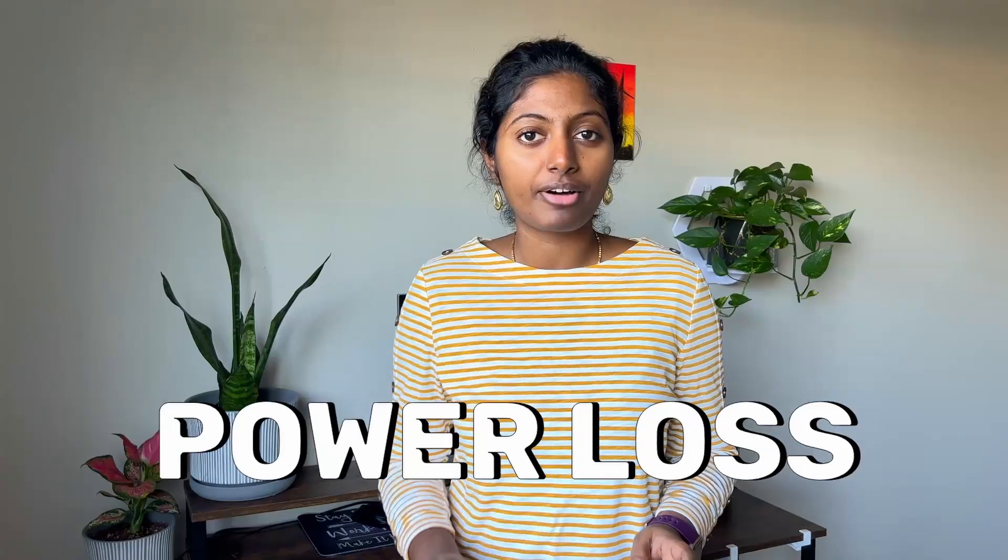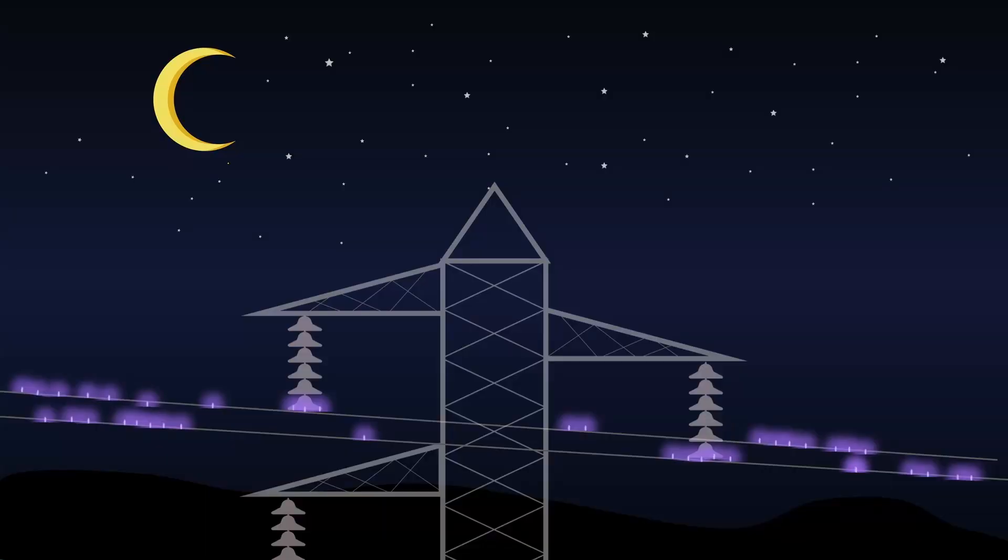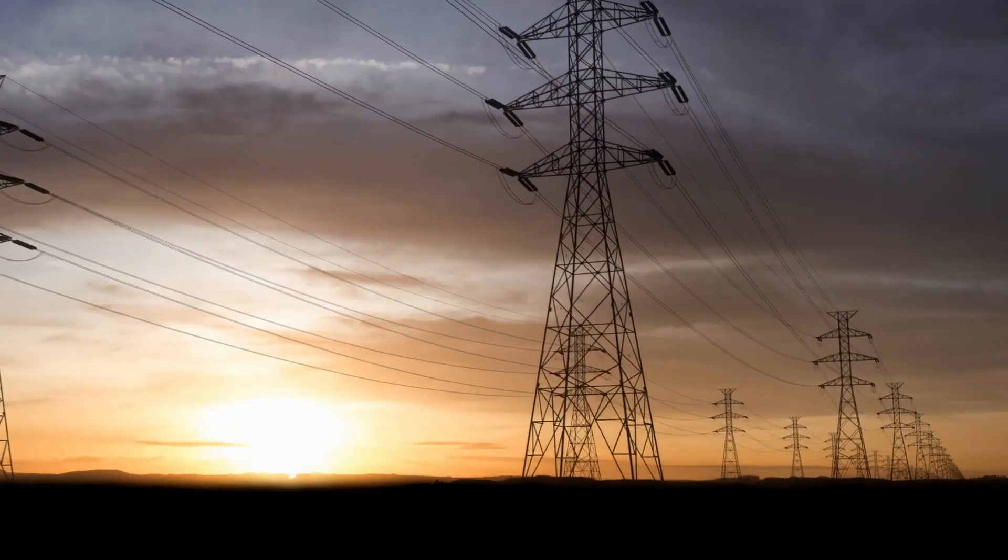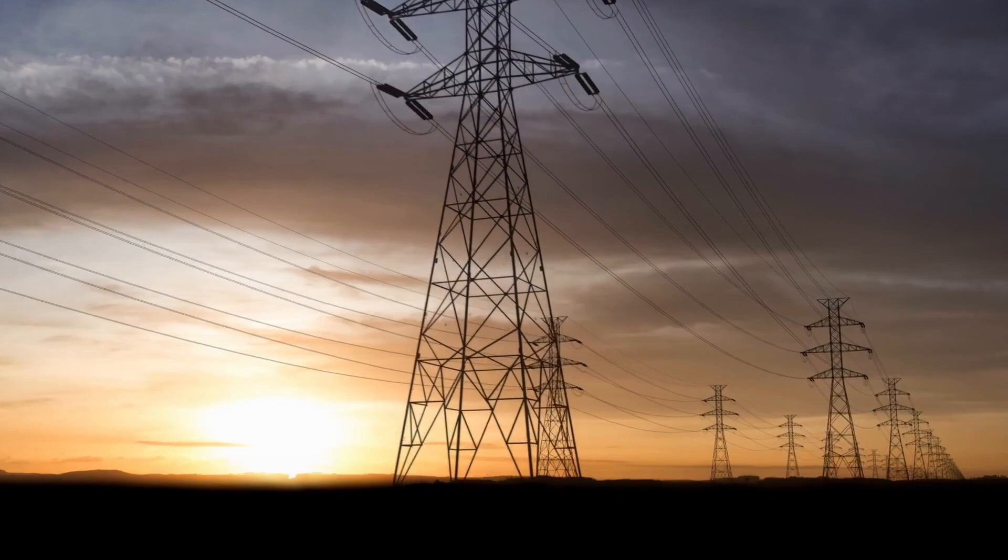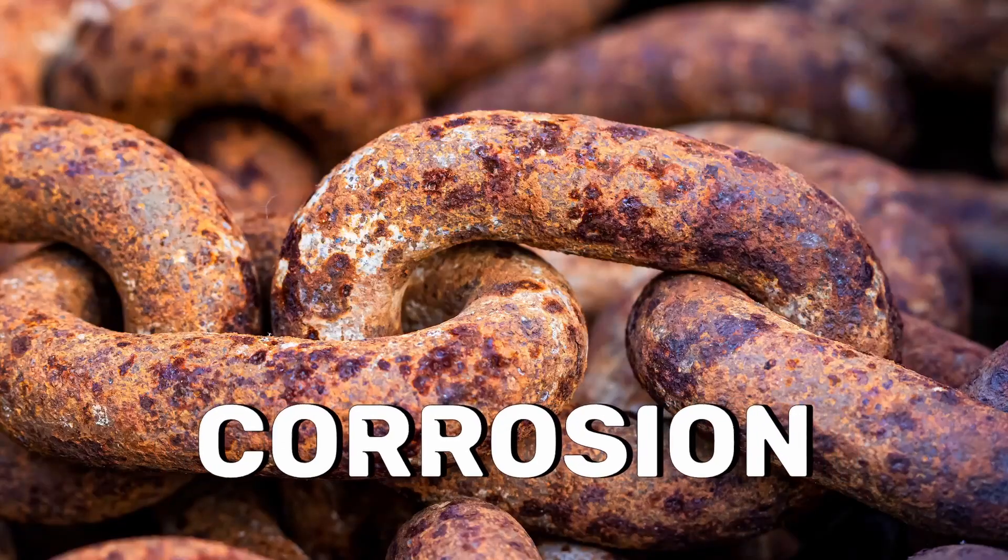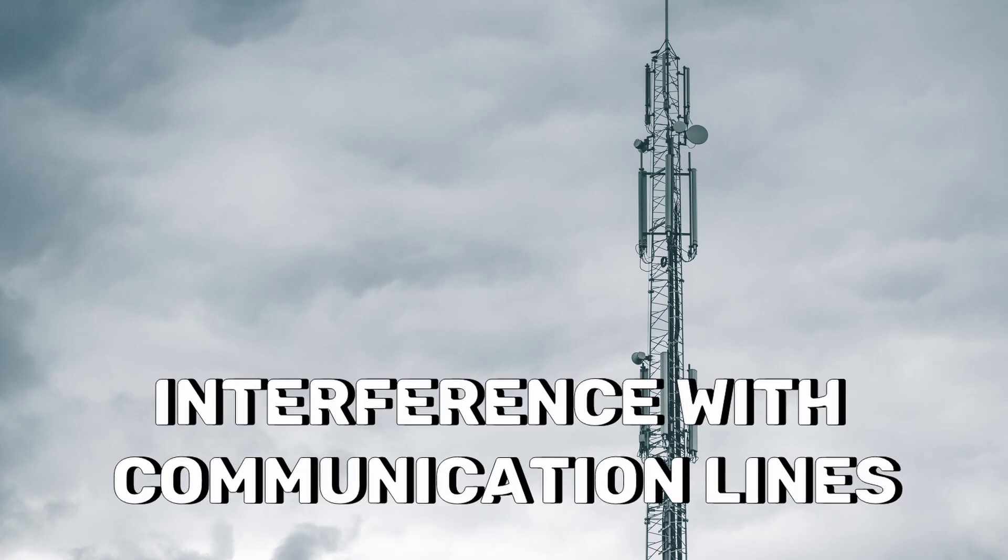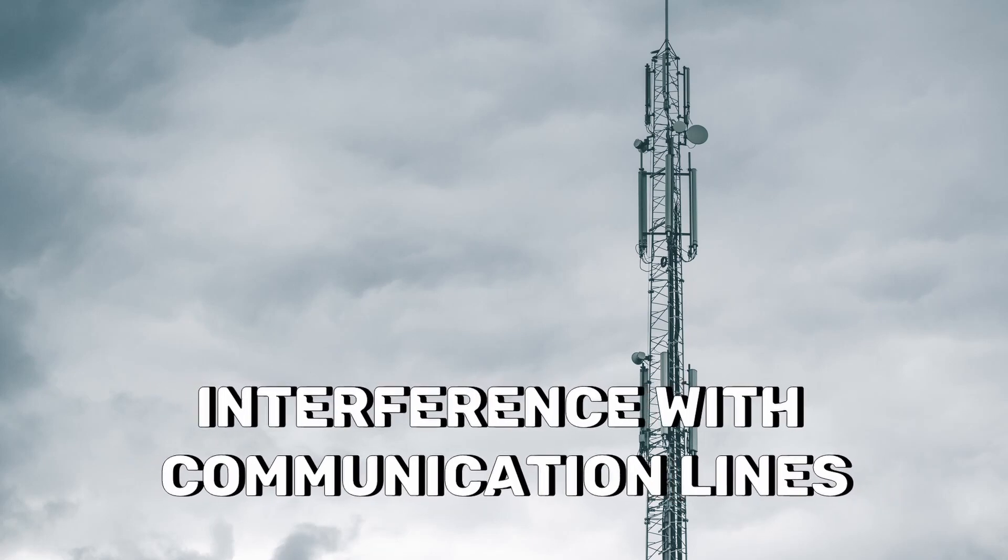First one is the power loss. Here the power is dissipated as heat and the violet glow. The second one is the ozone gas produced by corona may cause corrosion of the conductor. The third one is that it may cause interference with neighboring communication lines.